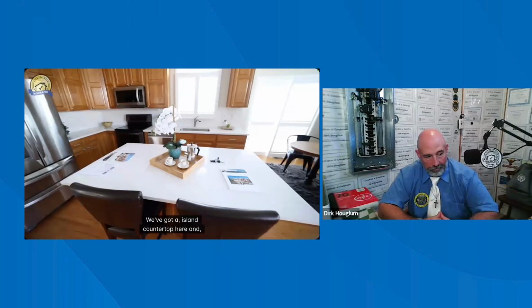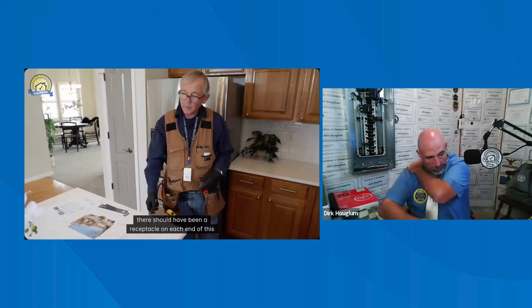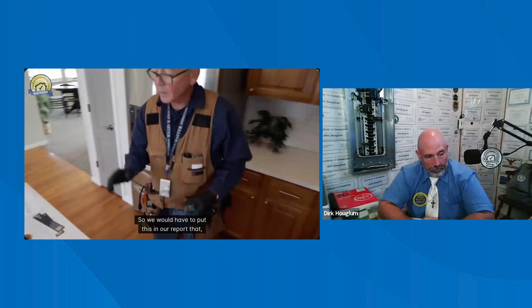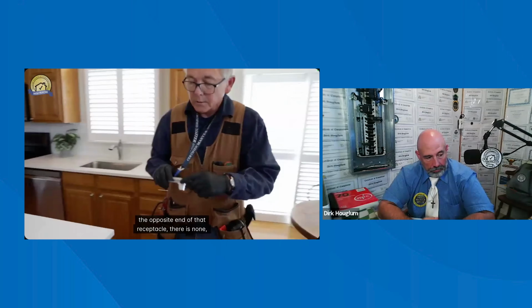We've got an island countertop here, and according to the code at the time this house was built, there should have been a receptacle on each end of this countertop, but right now there's just one. So we would have to put in our report that at the opposite end there is no receptacle, and we're going to recommend an electrician put one in on this end as well. The reason we do that is kitchen appliances only have a 3-foot cord, so we can't plug in an appliance on this end of the island without using an extension cord, and we don't like extension cords.